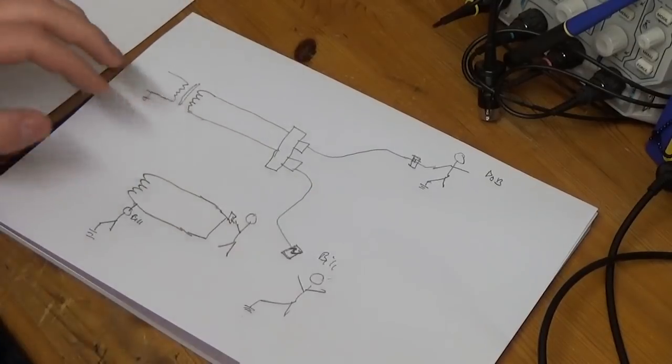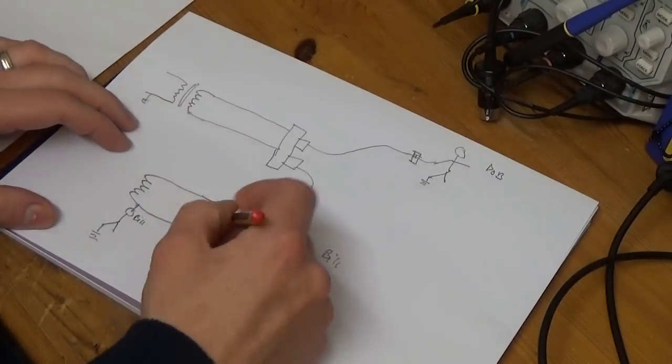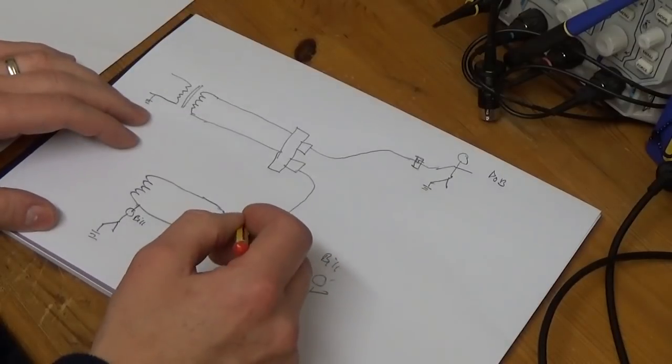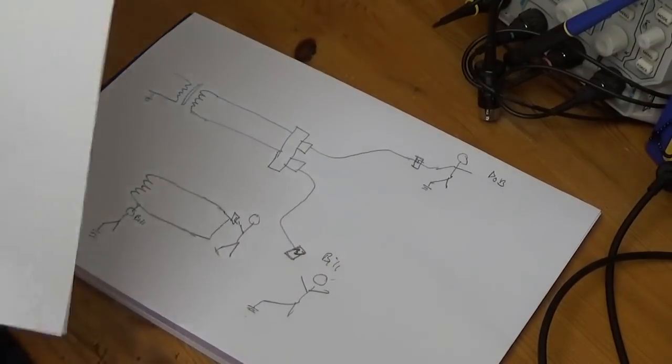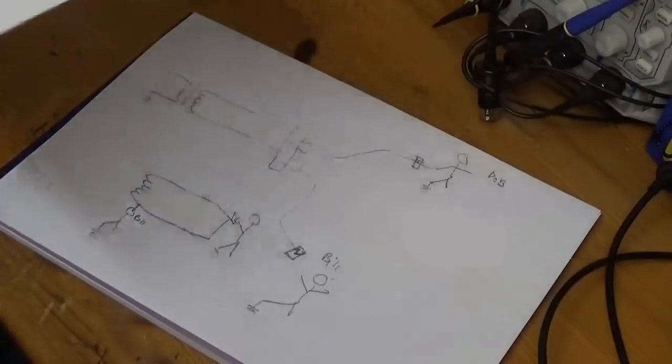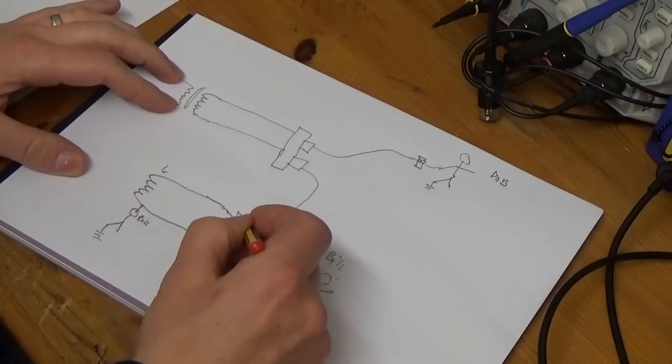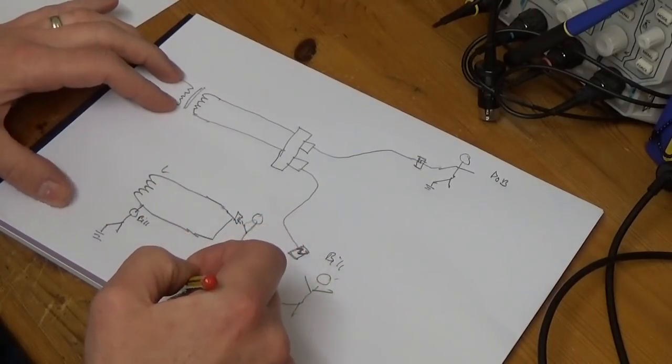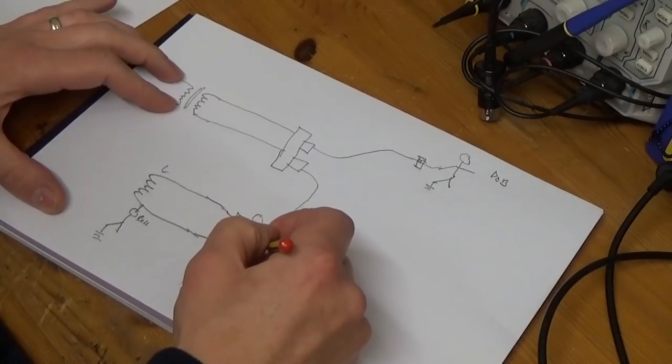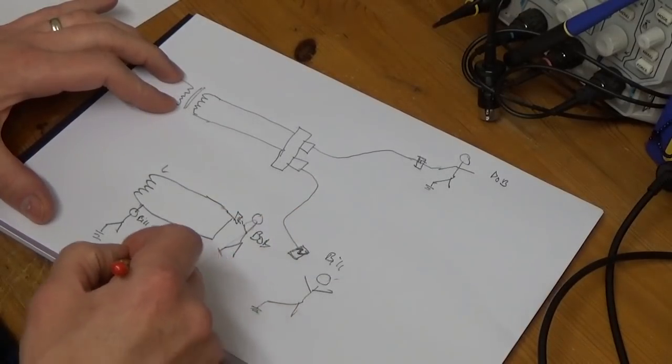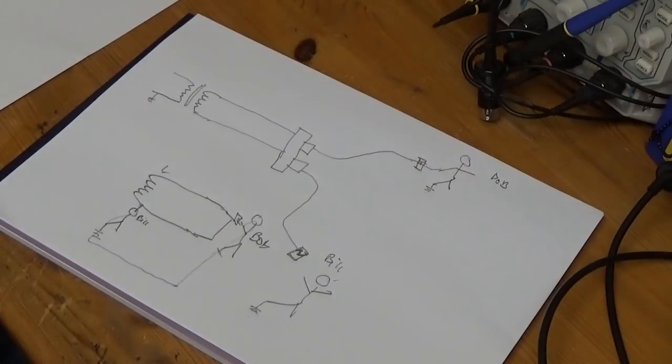So effectively what's happening here, Bill has referenced that side to ground, the neutral side. And poor old Bob here, he's got his line fault. He's gonna get himself a shock, or both of them really, because you've got that earth fault looping path like I was talking about. So effectively the line's gonna go through there, through the casing, through Bob, and then up through Bill. So there you have it, that's why two pieces of class one equipment, the shaver socket, shouldn't have two items of class one equipment.